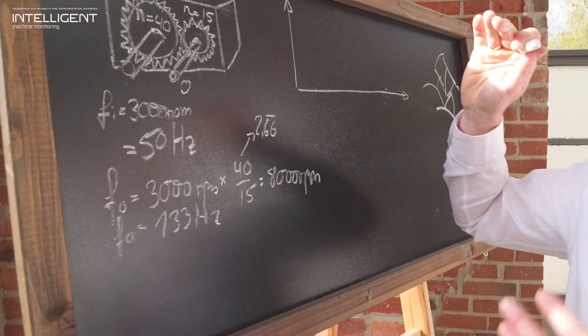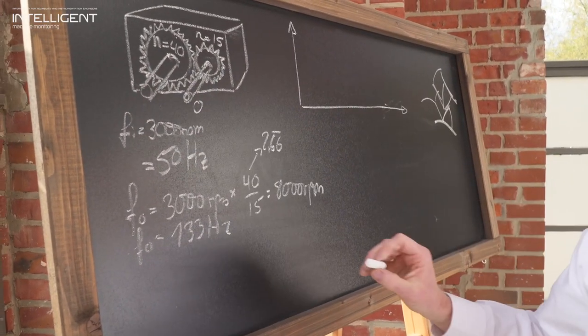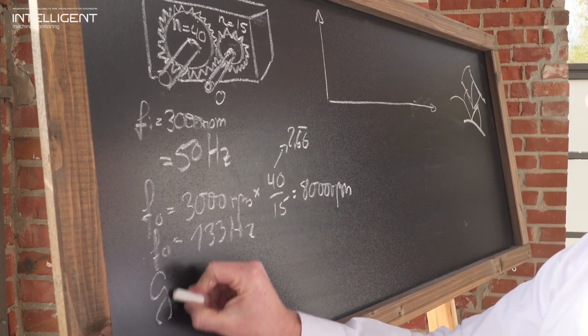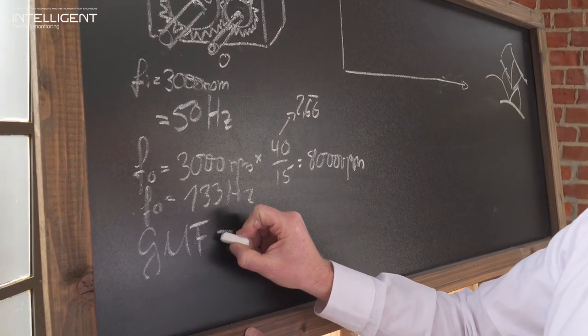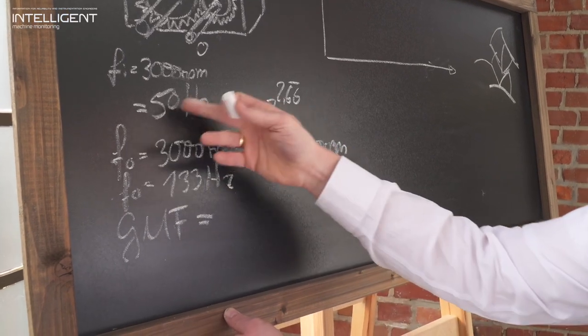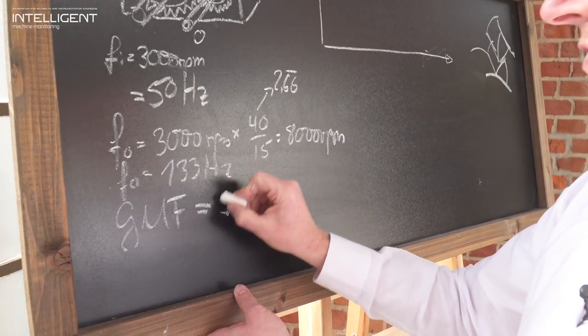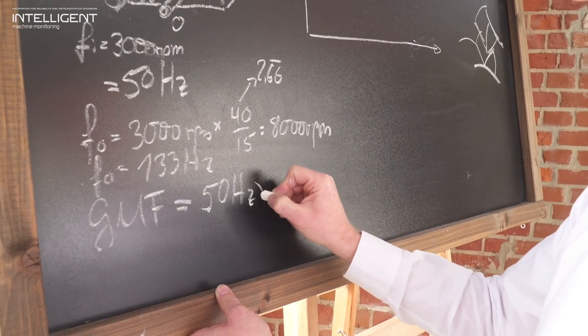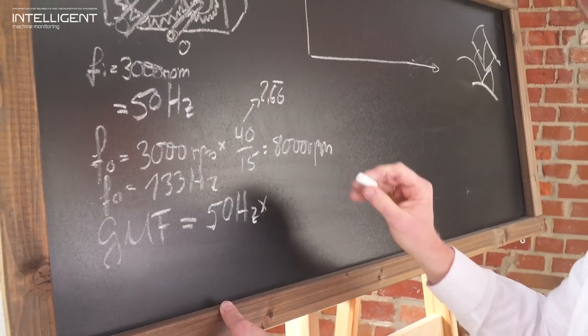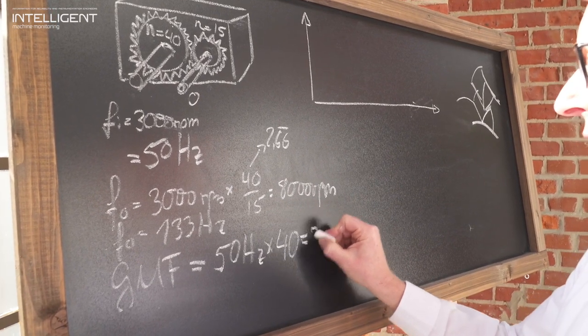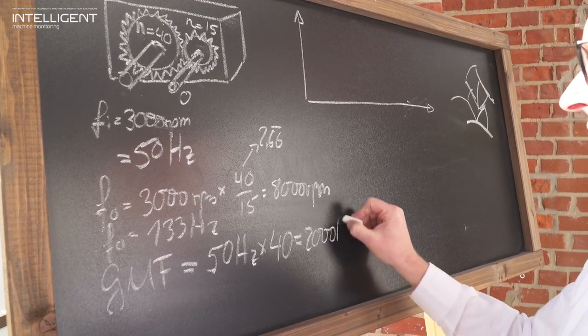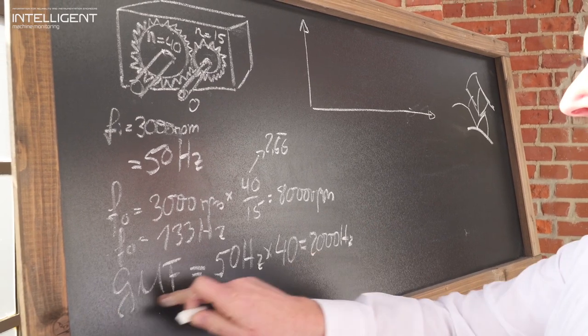So these are my speeds, and looking at the gear mesh frequency we have the turning speed of the shaft, so we have the 50 Hertz and multiply that with the number of teeth of 40 for the appropriate shaft, which results in a 2000 Hertz gear mesh frequency.